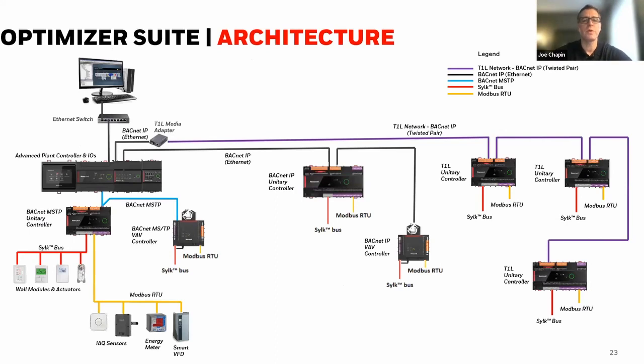This shows you the overall optimizer architecture. On the left-hand side, you've got your advanced controller. You go up to the right here where it says BACnet IP. At the top, they're taking a T1L media adapter. I'm looking at the purple line. They're sending this 1,000 meters to the first controller, and they're going 300 meters between controllers after that. You also have the ability where it says BACnet IP in the center. That's category 5 cabling, not necessarily T1L, twisted wire cabling. So you have all these different communication options.